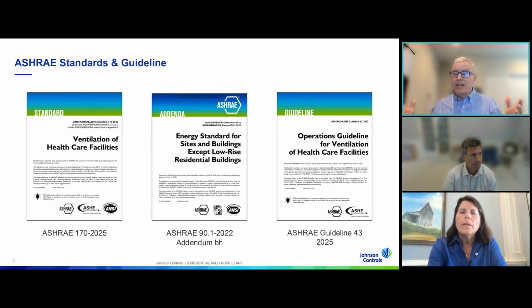Because as you start looking at the space, there's some resiliency that we need. But as we expand beyond those spaces, if we were to lose an air handling unit, that unit might be supporting multiple ORs. We can't have something like that happen. So I really encourage you to take a look at that guideline if you haven't seen it before, because it's got some really important information on how to mitigate those risks and also what to do if you have an excursion. What happens if you lose that relative humidity within that space? And it actually goes on, it's time-based. It looks at different times and says, if it's happened within an hour, you need to do this. So it's a really helpful guideline. And again, it's through ASHRAE and ASHE, and it's very much drawn from ASHRAE 170.